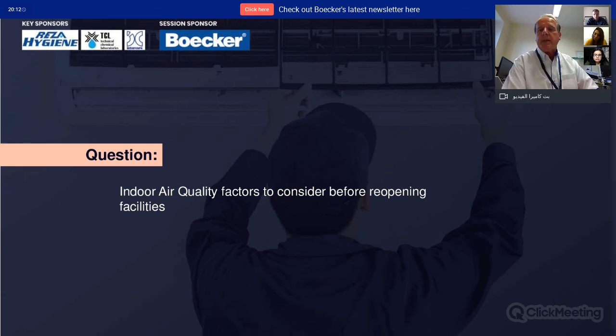And I guess the biggest failure I've observed is manufacturers' claims of how much cubic capacity these fogging machines can achieve - I think they're slightly overstated. The problem is achieving suitable coverage, the zone of effect of the equipment, and the contact time of the chemical on a particular surface are very, very difficult to validate.